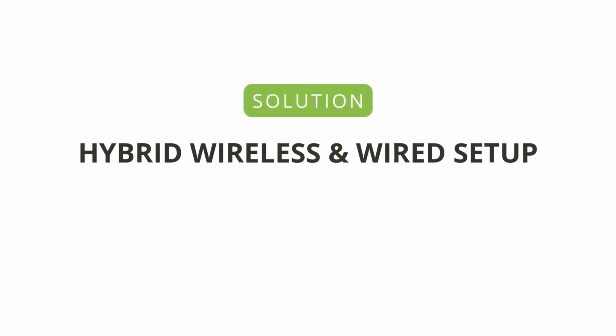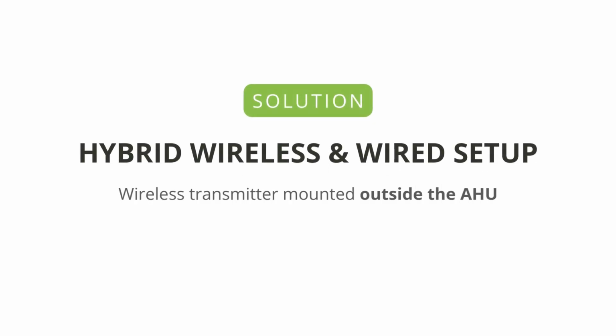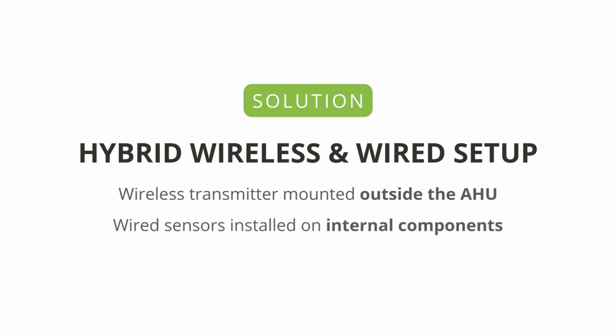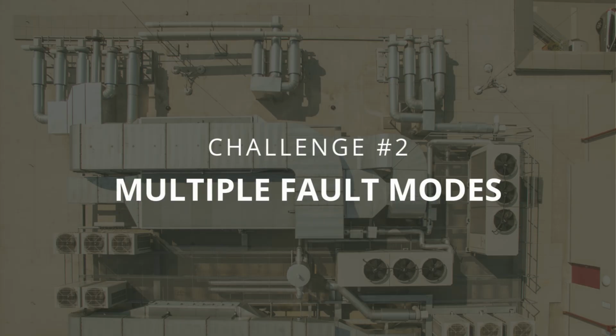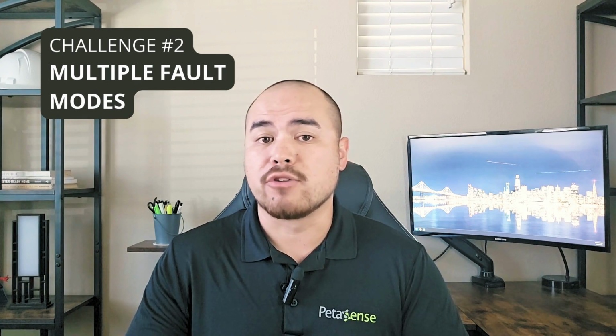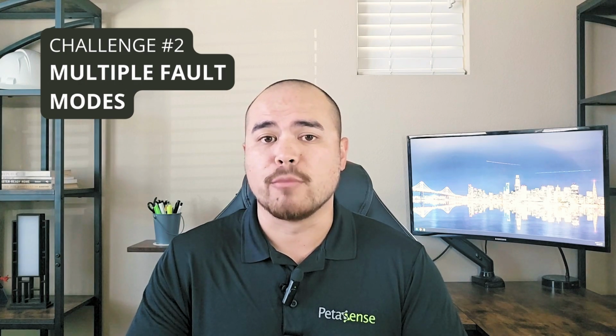The solution is to use a hybrid wireless and wired setup. We can mount a wireless transmitter on the outside of the AHU while wiring sensors directly to the internal components, like motor or fan bearings. Challenge 2. Multiple fault modes. Mechanical issues like bearing wear or belt misalignment are only part of the picture. It's recommended to monitor additional parameters like airflow and motor health, especially in regulated environments like pharmaceutical manufacturing.